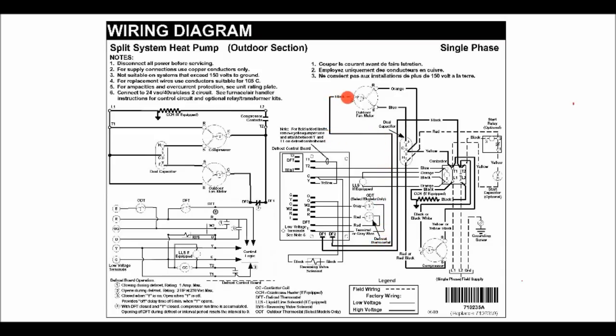This is going to help you if you're following behind another company or another technician who happened to wire something differently. Or if you remove wires and can't remember where they go back, where they're connected back to, this is going to give you a wire by wire, color by color connection. And it's the actual physical connections that you'll see inside of the air handling unit or the outdoor condensing unit.